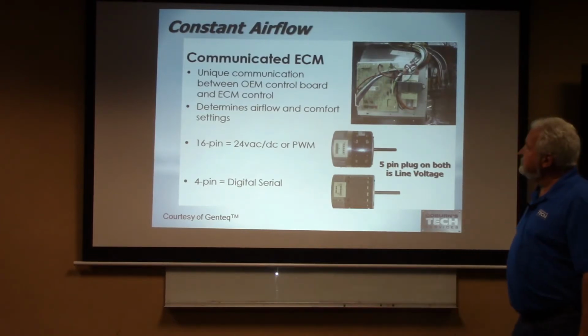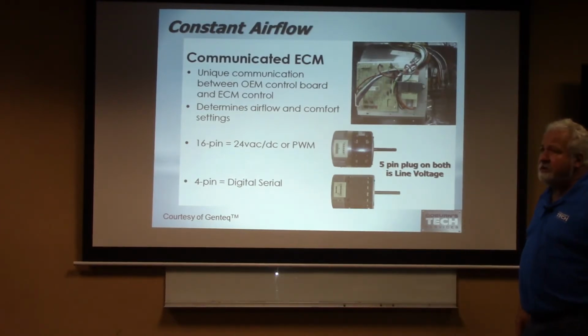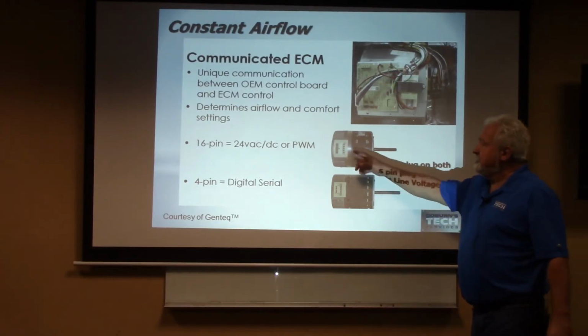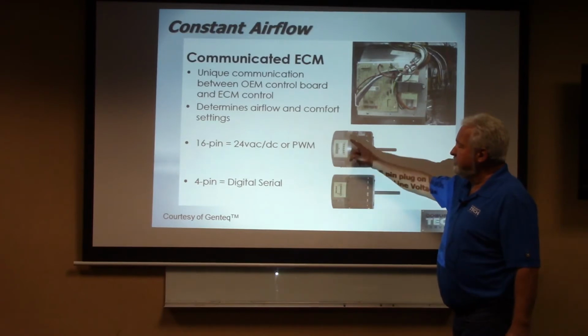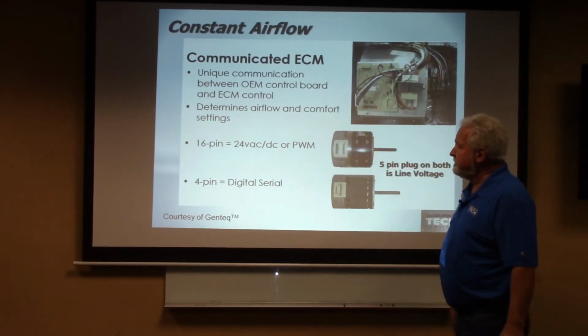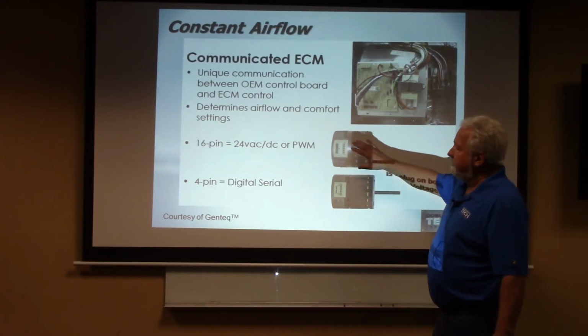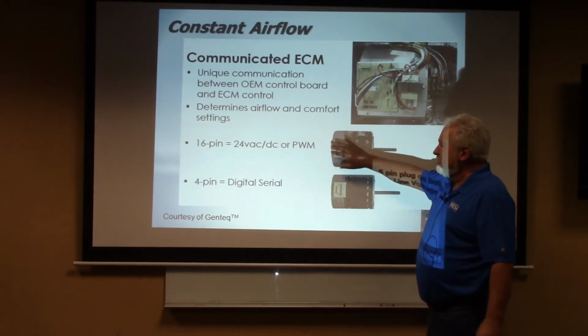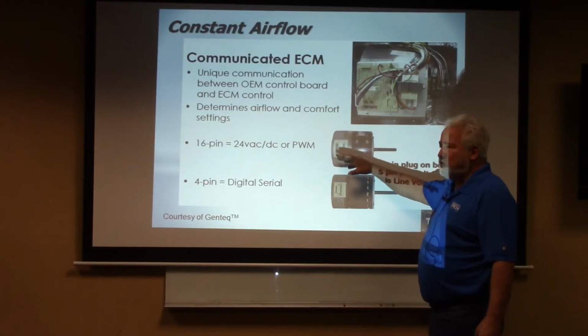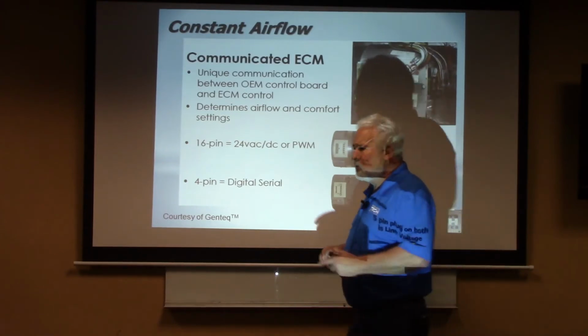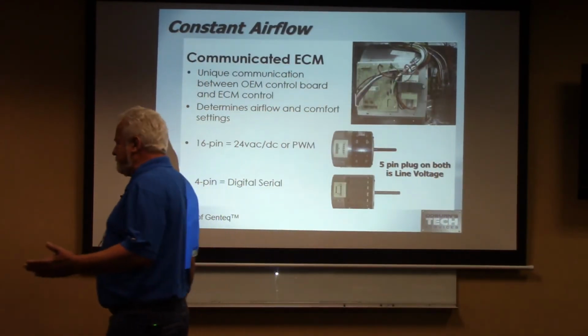Constant airflow motors, these are those ECM motors with the variable speed, true motors. They're going to either be a 16-pin or a 4-pin typically on the Genteq side of that deal, and it's going to have 24-volt AC, DC, pulse width modulation. Again, that's where we're going to come back to the manufacturer specific.